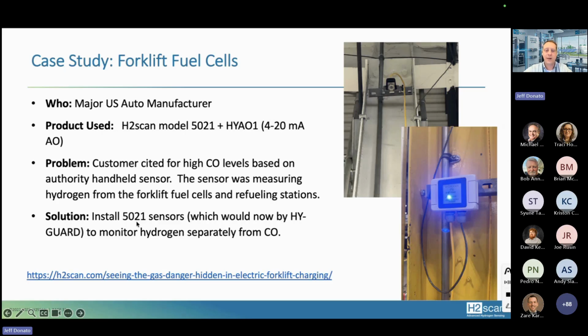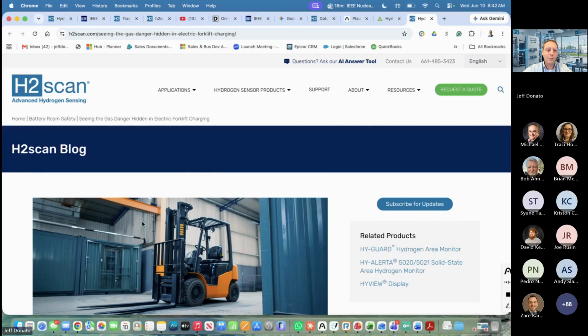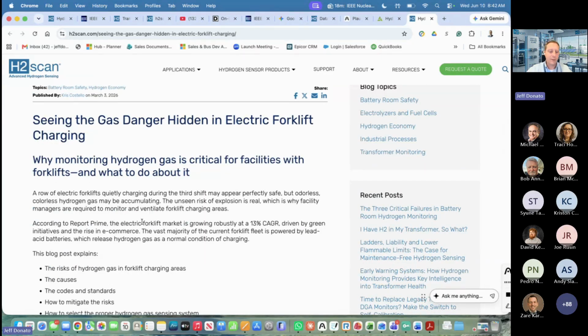So if you have to differentiate between CO and hydrogen based on something that is producing hydrogen, it could be a fuel cell, it could be a battery system that's being charged. They could use hydrogen sensing along with their CO sensors so they can differentiate between the two. And in this case, they connected it to their HVAC system, and based on the reading that they were getting from the 4 to 20 milliamp signal, they would ramp up their fans to mitigate the hydrogen as it would accumulate. There's also another article that we wrote on that situation that's also on our website, and you can also look at that blog as well and read all about that.